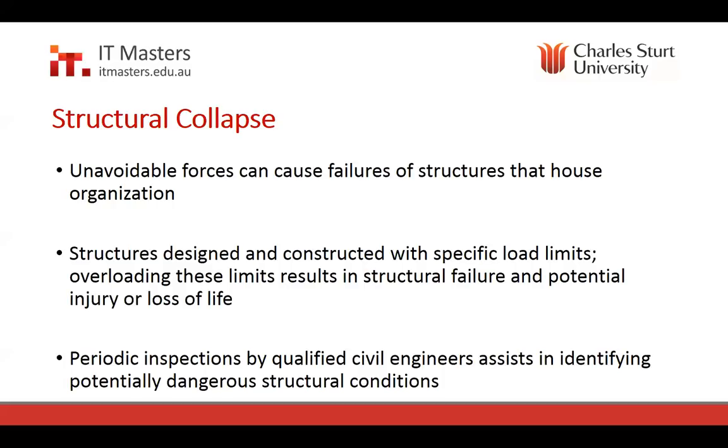And they ended up with cabinets crashing a couple of feet down onto the concrete floor, which ended up in some cut cabling and cut power wires and damage and all sorts of things. So that's something to think about in terms of structural collapse. It doesn't necessarily mean that the whole building's going to collapse, but that the supporting services, the supporting flooring or other infrastructure, even cable trays, if they're overloaded, can collapse as well. So think about that as well. That's something that we need to think about.